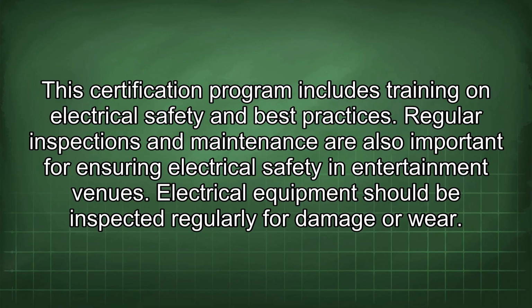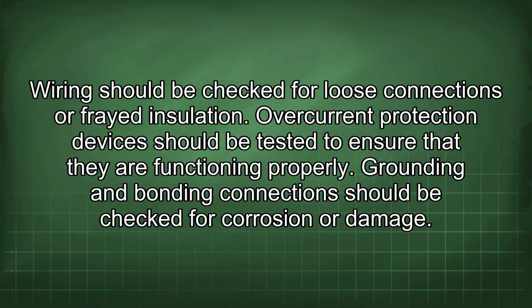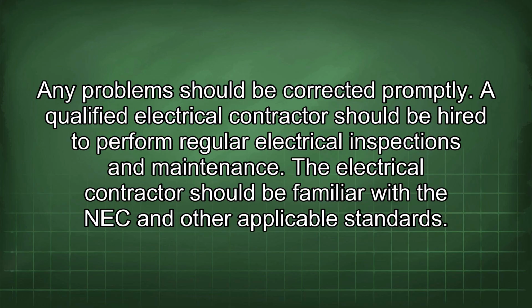Regular inspections and maintenance are also important for ensuring electrical safety in entertainment venues. Electrical equipment should be inspected regularly for damage or wear. Wiring should be checked for loose connections or frayed insulation. Overcurrent protection devices should be tested to ensure that they are functioning properly. Grounding and bonding connections should be checked for corrosion or damage. Any problems should be corrected promptly.